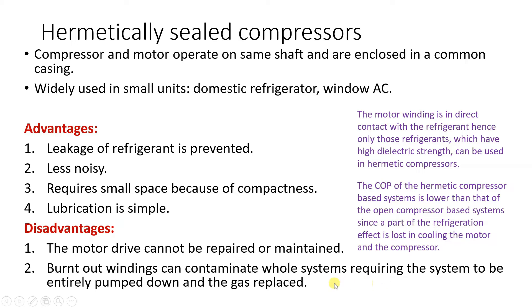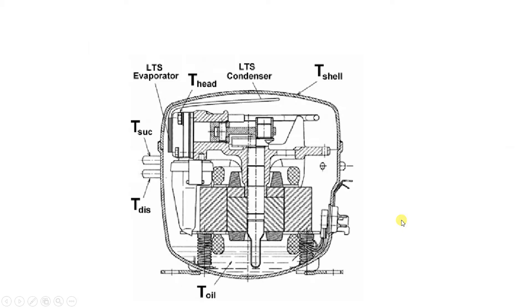The COP of hermetic compressors is lower than open compressors because part of the refrigeration effect is lost in cooling the motor and compressor. Now looking at the diagram: here you can see suction and discharge tubes welded or brazed to the outer shell. Gas enters the shell from the suction side, and there is an oil sump at the bottom with an oil pickup tube. Wherever lubrication is required, there is a small hole so oil is sent to that location.